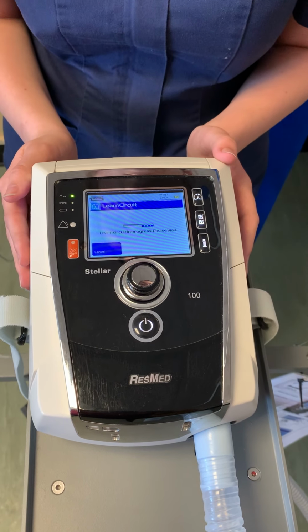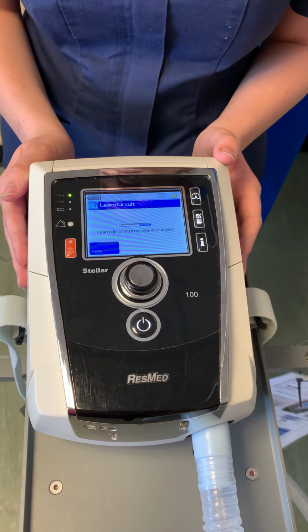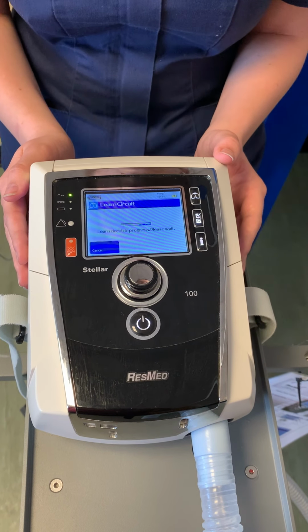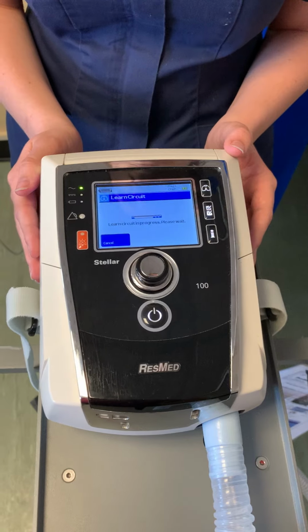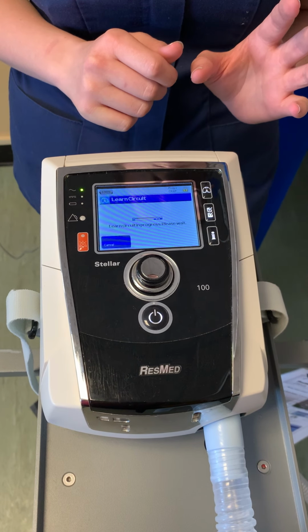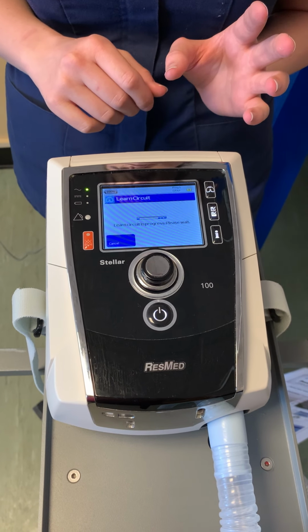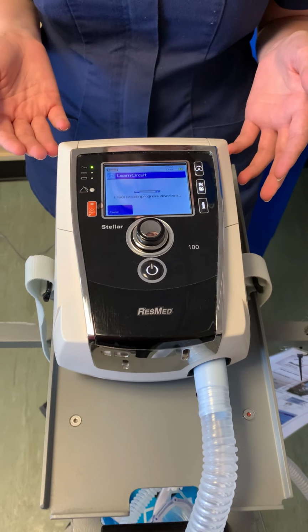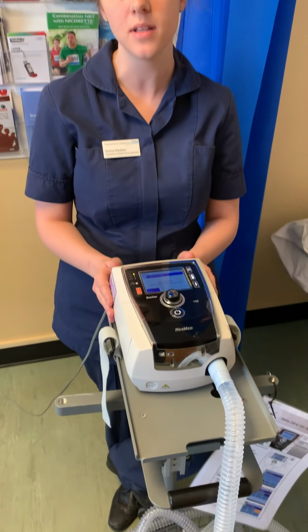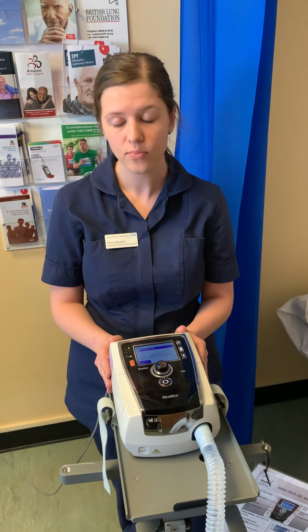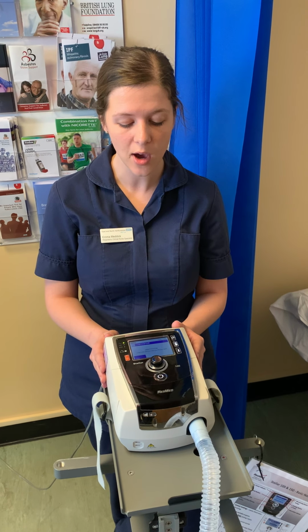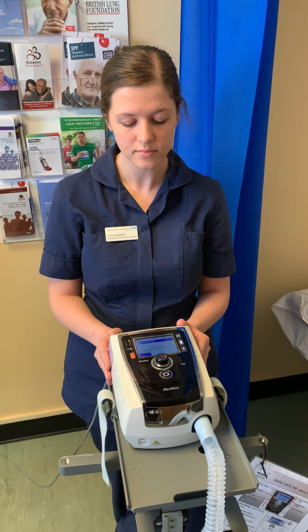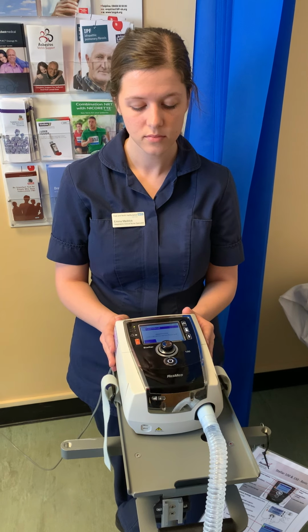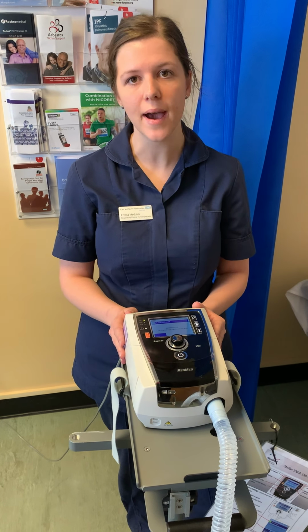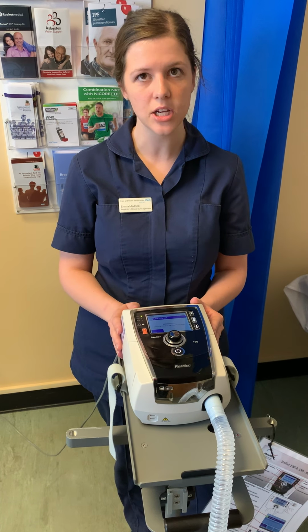It's very easy. You just press start and it does it for you and lets you know if it's safe. I would also always say, if it fails the first time, check all your equipment, make sure it's all on tightly and the correct way, and try again. If it fails again, look to get new equipment and see if anything is faulty. So we'll just wait for that to complete. It only takes a minute or so. You should do this in between every patient and any time you change the ventilator tubing.